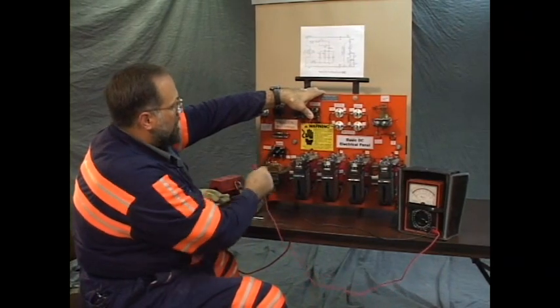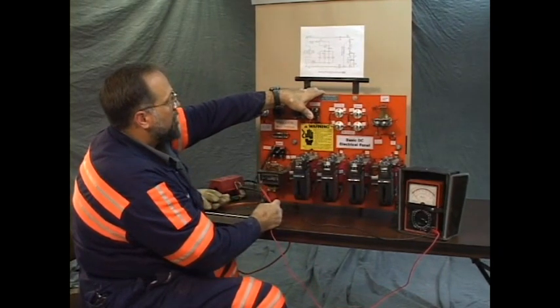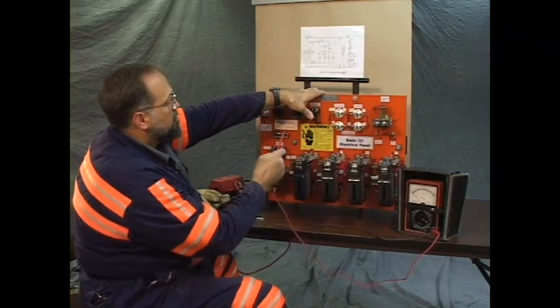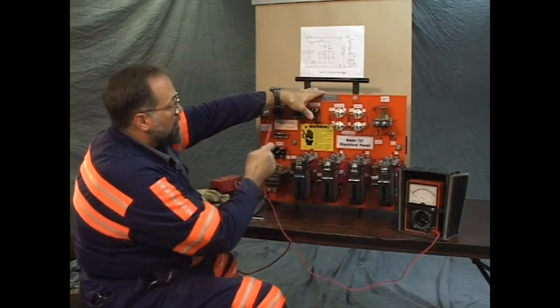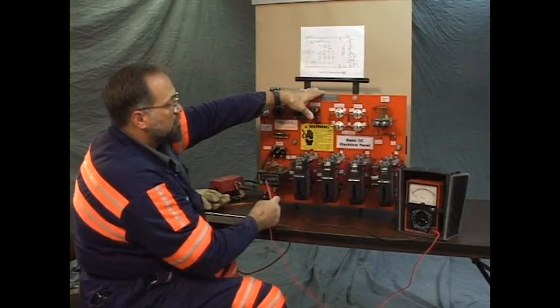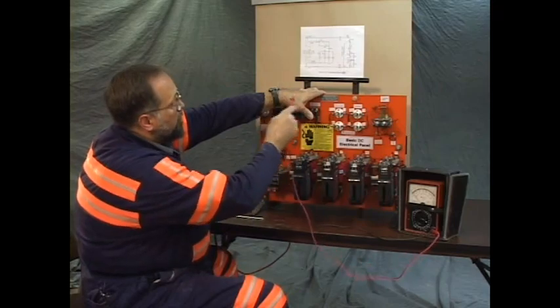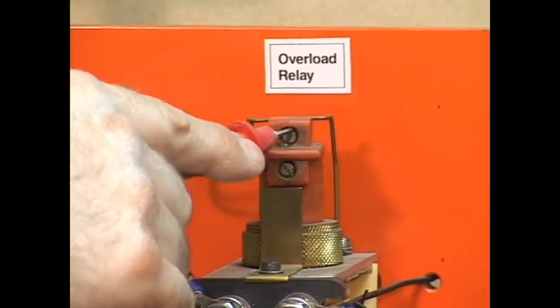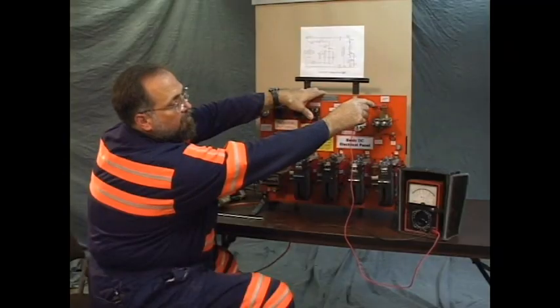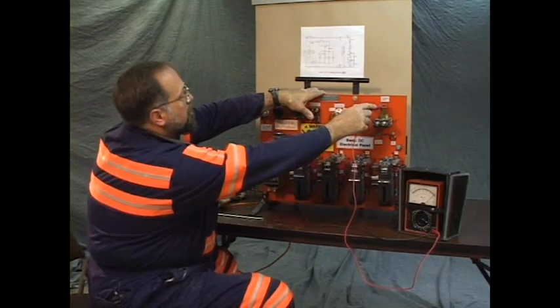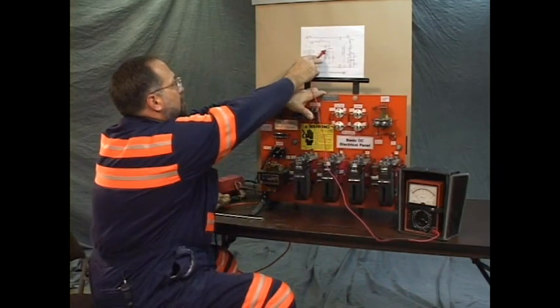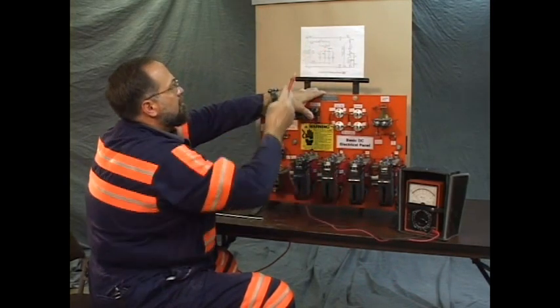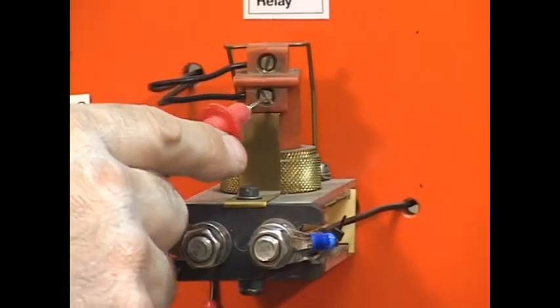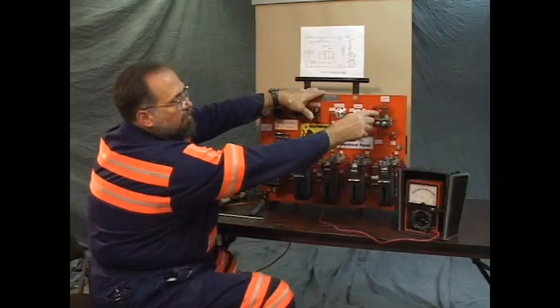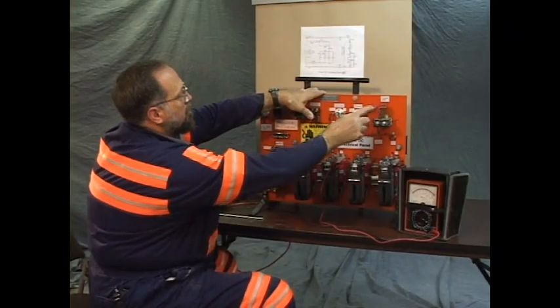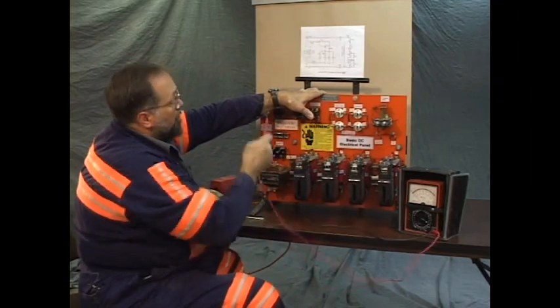Now, to remain attached to the positive side of the rectifier, I'm going to complete the rest of this troubleshooting on this side by holding the start switch in the depressed position. The next point is OL1, the mercury tube on top of OL1, and we have a circuit. That is the line side of that device. The load side is the bottom of OL1. And there you have it.